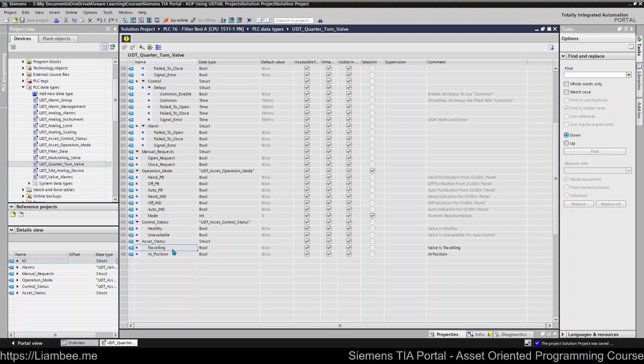Some of the things to realize are you can change UDTs as you develop, but we'll come on to it when we do the library management, that you should really try and get your UDTs finalized before you put your system out into production, or you deliver it to a client, or it's in a position where it's actually controlling something, because changing UDTs constantly, especially ones that are base objects for other UDTs, can become very messy if you're not really sure what you're doing.